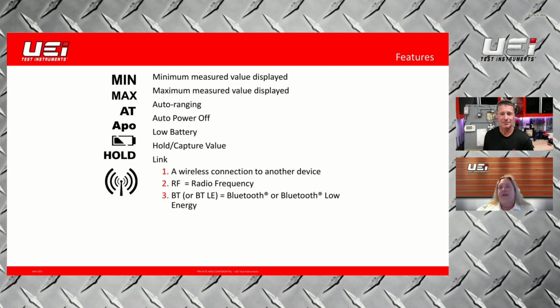There are some other nice features and different symbols to be aware of on your meter. We talked earlier about inrush current, and I mentioned max capture, but inrush happens so fast that even max generally can't capture it. But when you're looking at something over a period of time, it may be very handy to get that max capture or minimum capture while monitoring the system.